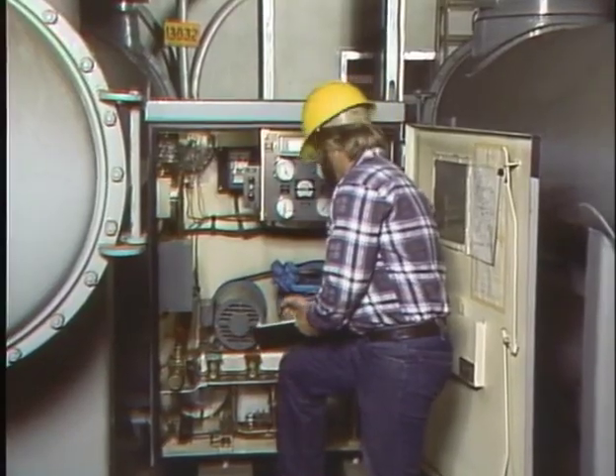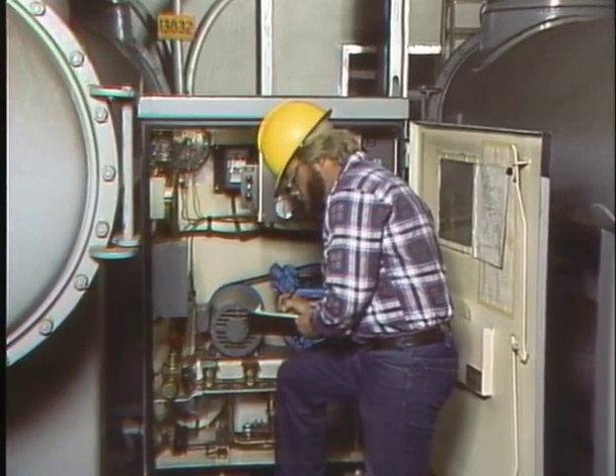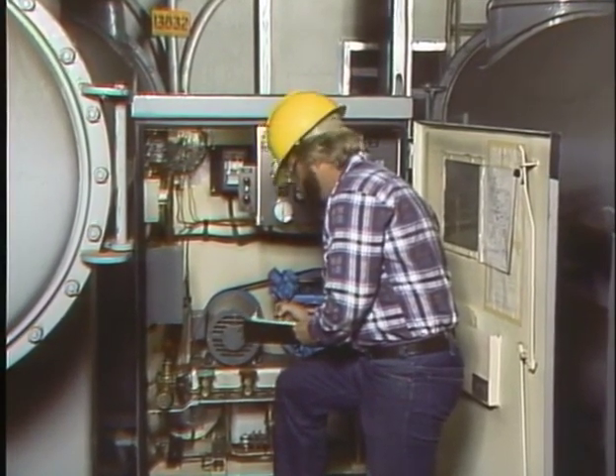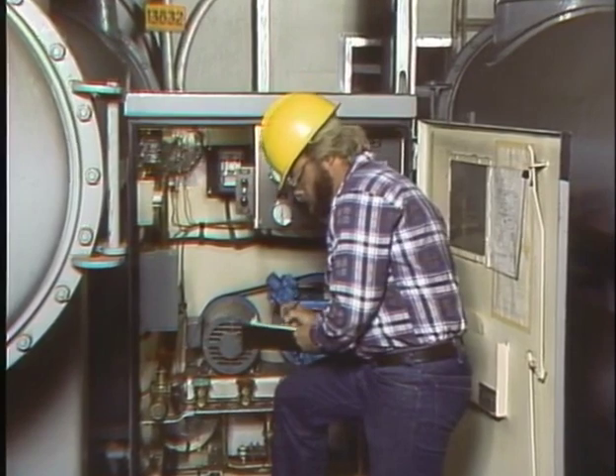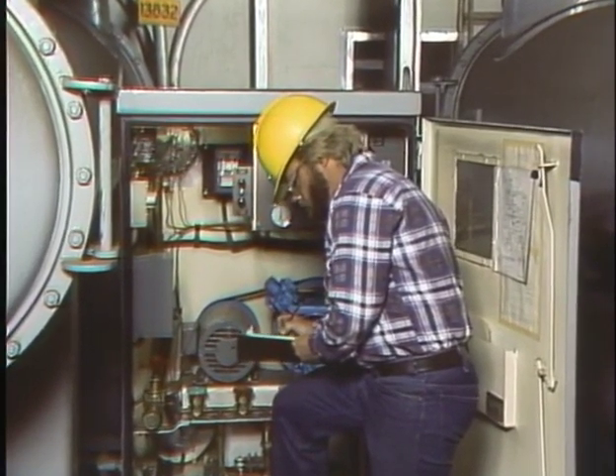in service. In this part of the program, we're going to look at common checks that are made during a post-installation inspection. These include mechanical checks of the circuit breaker and mechanical checks of the breaker's operating mechanism. Keep in mind that these checks may also be performed during maintenance of circuit breakers that have already been in service. An important part of inspecting a breaker prior to putting it in service is documenting the status of the breaker. This is important for a couple of reasons.